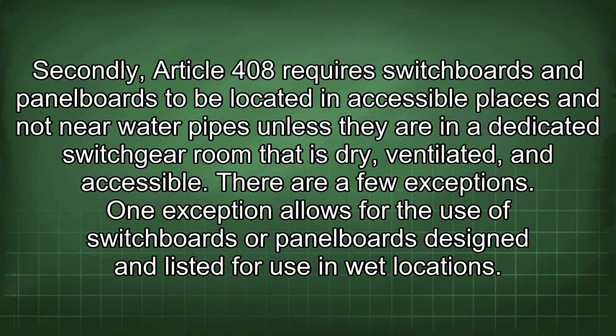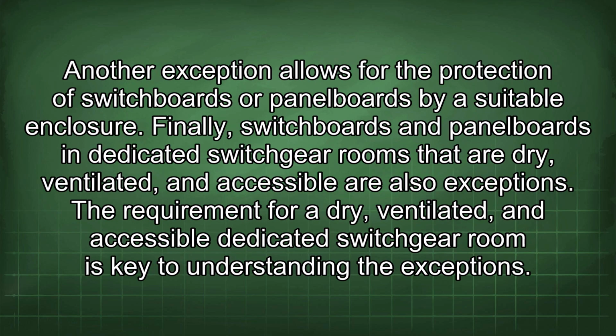Secondly, Article 408 requires switchboards and panel boards to be located in accessible places and not near water pipes unless they are in a dedicated switchgear room that is dry, ventilated, and accessible. There are a few exceptions. One exception allows for the use of switchboards or panel boards designed and listed for use in wet locations. Another exception allows for the protection of switchboards or panel boards by a suitable enclosure. Finally, switchboards and panel boards in dedicated switchgear rooms that are dry, ventilated, and accessible are also exceptions.